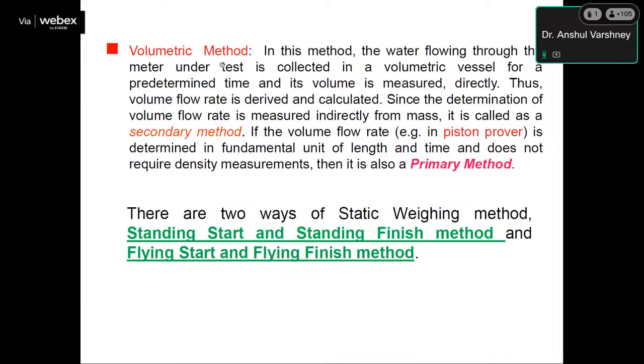The next method is the volumetric method. In the volumetric method, the water flowing through the meter under test is collected in a volumetric vessel for a predetermined time, and its volume is measured. Thus, volume flow rate is derived and calculated. Since the volume flow rate is determined indirectly from mass, it is called a secondary method. If the volume flow rate is determined in fundamental units of length and time and does not require density measurement, it is called a primary method.